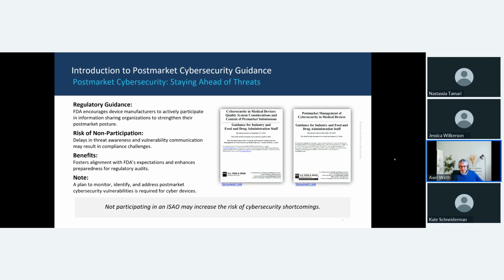Specifically now, switching over to where the FDA comes in, we have currently the two guiding documents from the FDA, the 2023 pre-market cybersecurity guidance and the 2016 post-market cybersecurity guidance. Both do reference the role and importance of ISAOs. Specifically, FDA encouraged device manufacturers to actively participate in information sharing organizations to strengthen their post-market posture and obviously also produce more secure products in the end. There are certain risks in non-participation. For example, your awareness of threats may be delayed. Your communication about newly discovered vulnerabilities may be delayed. That may result in compliance challenges.